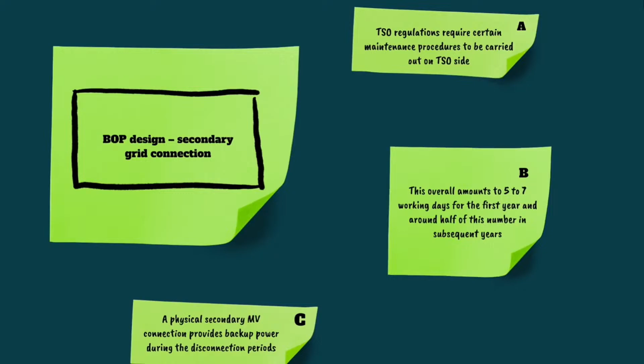Generally, the TSO requires certain maintenance procedures on their side of the grid connection, on the substation that has been put into operation, once your wind farm is up and running. This is something they are routinely doing using their own resources and their own planning. Typically you would encounter at least 5 to 7 working days devoted to an almost complete shutdown on the TSO side for the first year of operations, and roughly half of that in subsequent years.